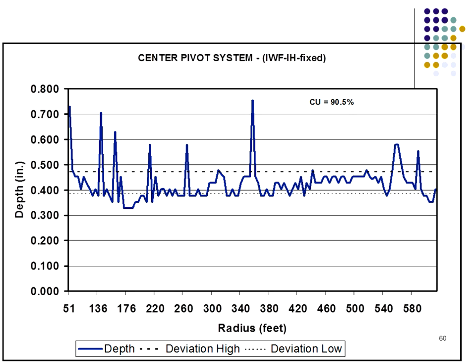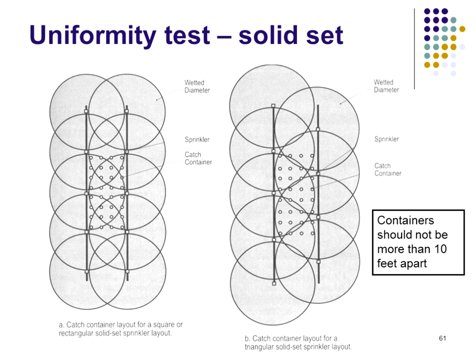The next one here, this one was at 90%, and even though it's got a couple spikes here, it's not as high because you have to look at how this range is set up on here. But you can see most of the readings fall within this plus or minus 10% on this range. And this here might be one spot. It could be splashing off a tower. It could be a rubber boot that's got a leak.